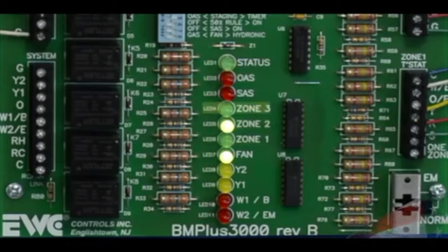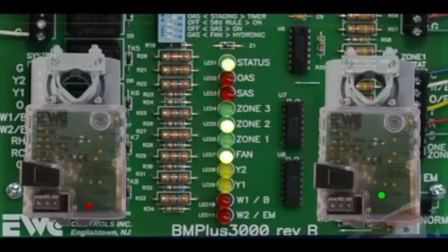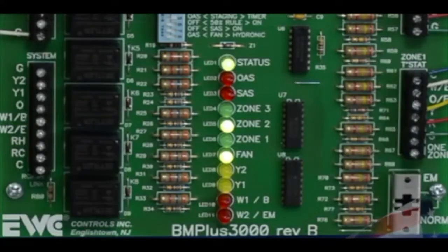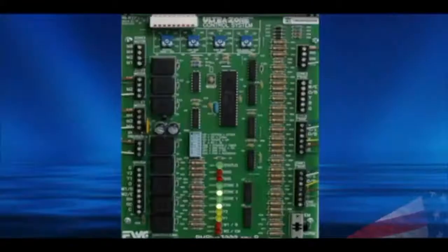The damper LEDs let you know the powered position of the damper terminal for the particular zone. Green open, off closed. When using the EWC URD style damper, the LEDs on the dampers will indicate the actual position of the damper. This gives you a precise visual inspection of damper operation up to 60 feet plus away under a house or in an attic. The system LEDs show the operation of the equipment where 24 volts is energized. These LEDs are in series with a relay coil and are essential to system diagnostics.